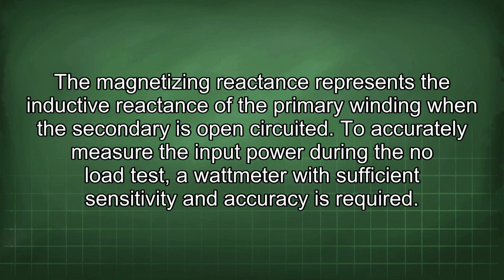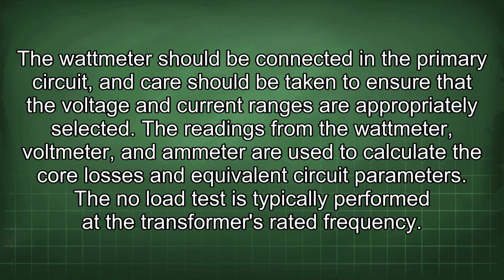To accurately measure the input power during the no-load test, a wattmeter with sufficient sensitivity and accuracy is required. The wattmeter should be connected in the primary circuit, and care should be taken to ensure that the voltage and current ranges are appropriately selected. The readings from the wattmeter, voltmeter, and ammeter are used to calculate the core losses and equivalent circuit parameters.